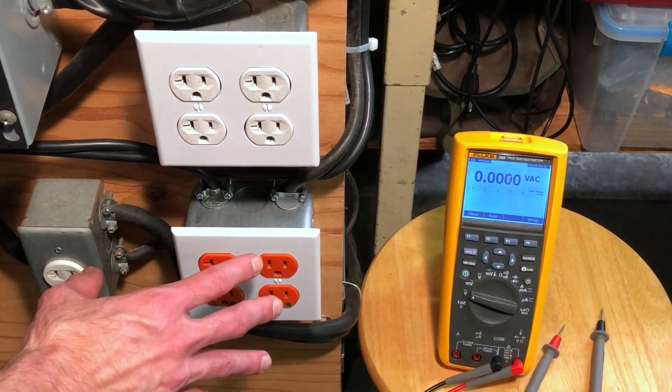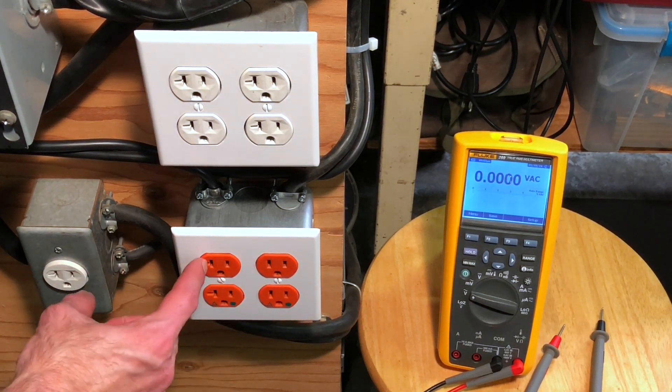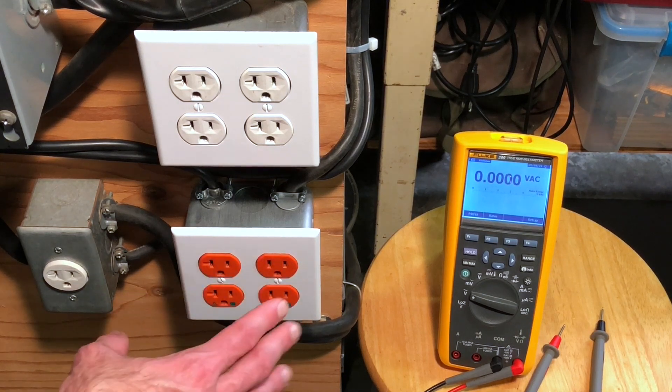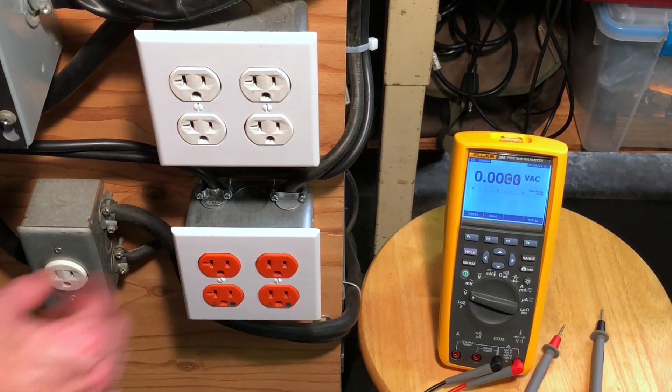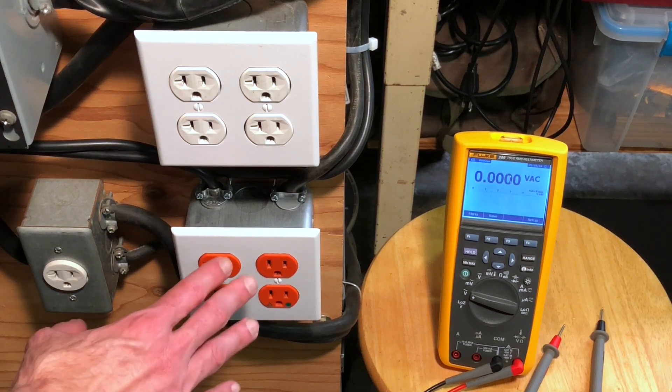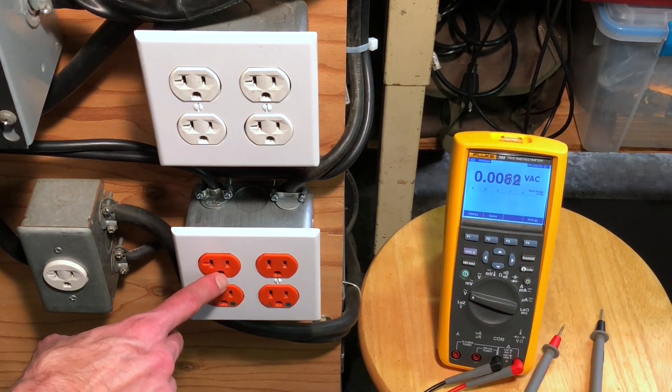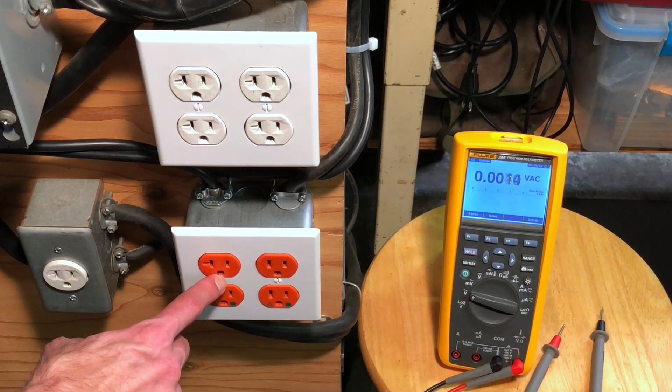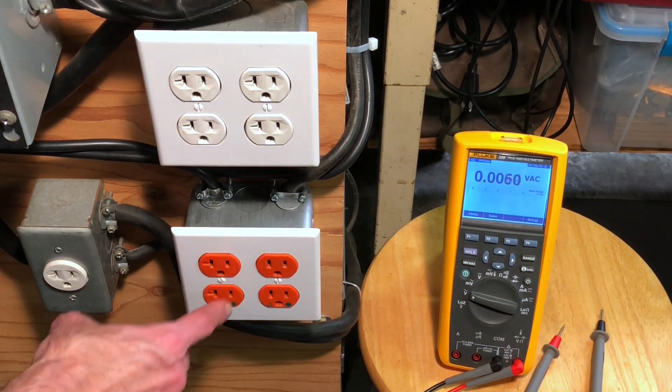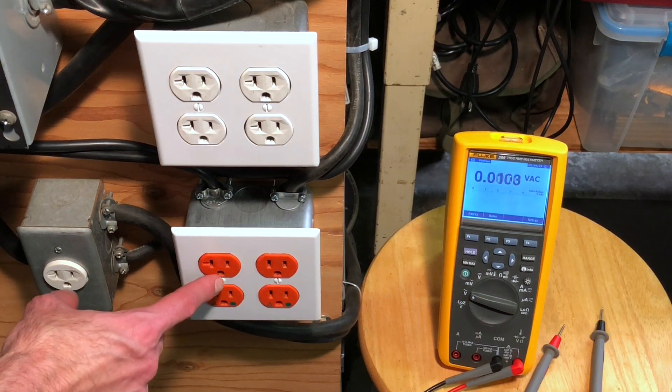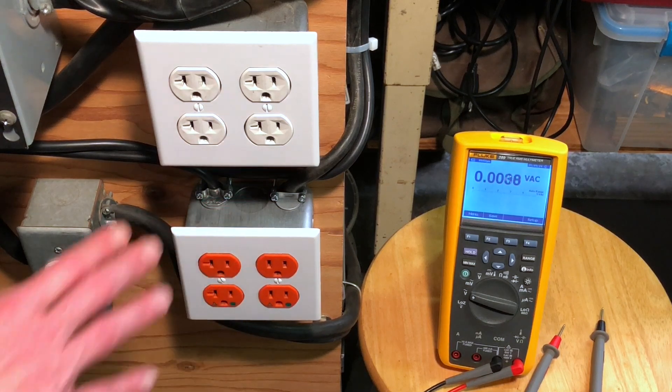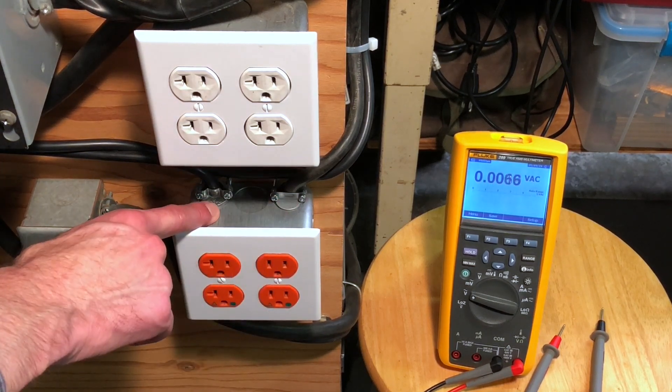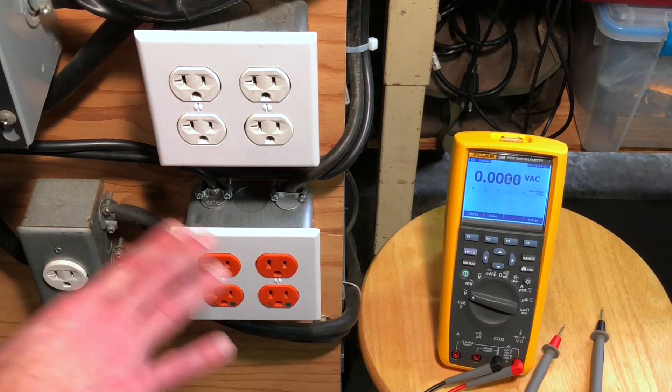Down here, these are all my isolation transformers. There's one transformer on this group and another on this group. The only difference is this is a smaller VA rating transformer. It's not turned on right now, so we'll just use this side over here. They're orange-colored outlets because these are isolated ground outlets, meaning that this little ground socket right here is electrically not connected to the mounting bracket that's part of the outlet assembly.